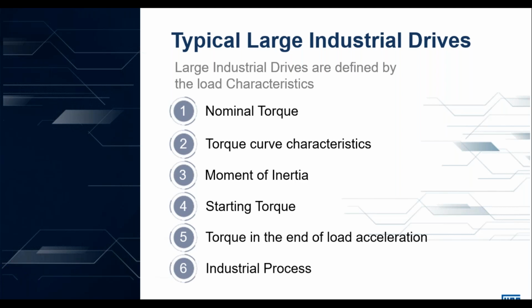When we talk about large drive systems, these are generally not off-the-shelf solutions. These would be motors that are specifically designed in most cases for a certain load or a certain application. Unlike a low voltage motor, which would generally be bought off the shelf and needs to already be technically compliant to a large range of loads and applications, in the large motor solution environment, this is not the case. We would need to, or we do design the motor more specifically for its application. With that being said, there's some critical design information that is needed to correctly specify and supply a large machine.